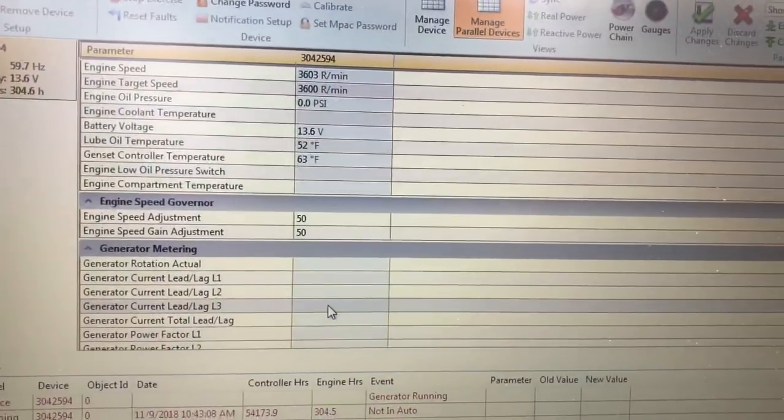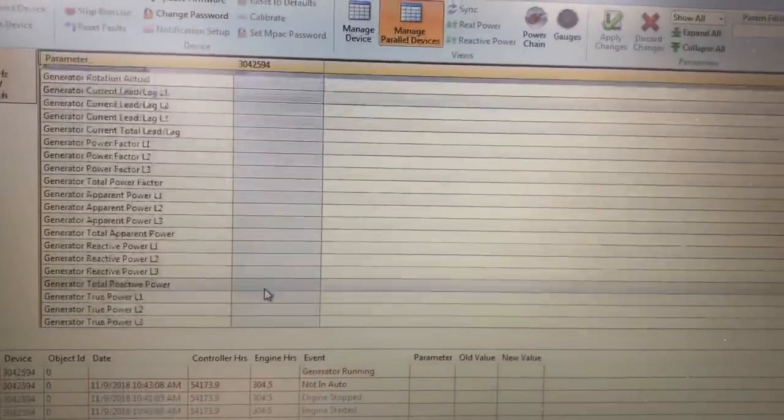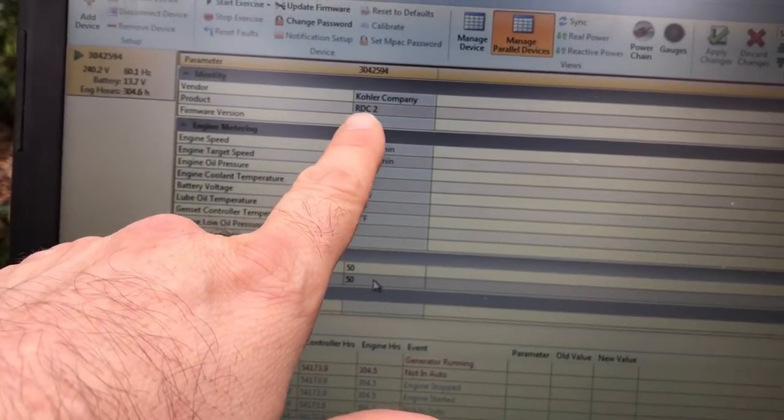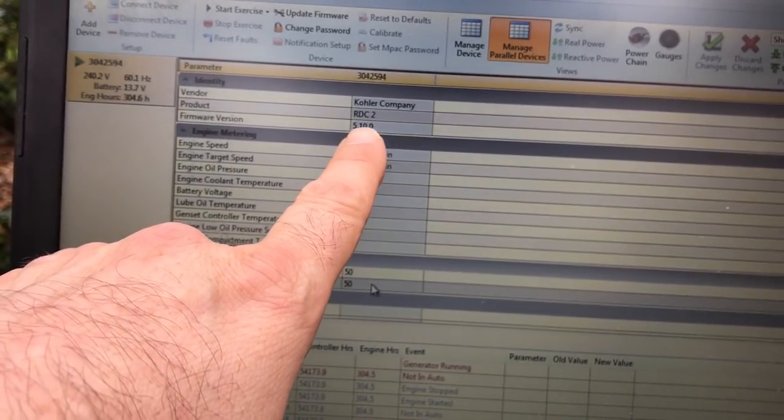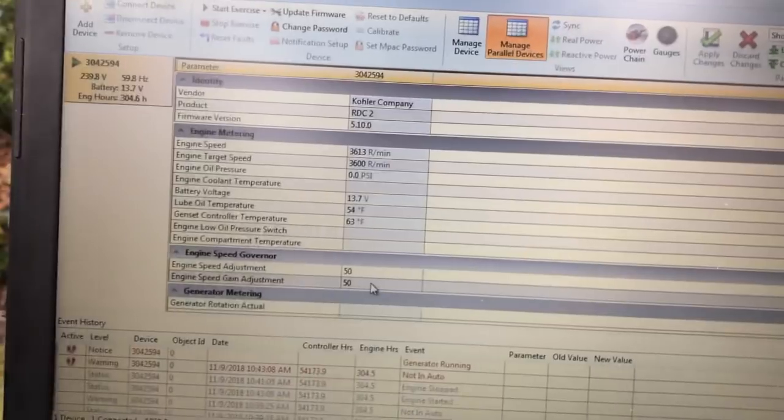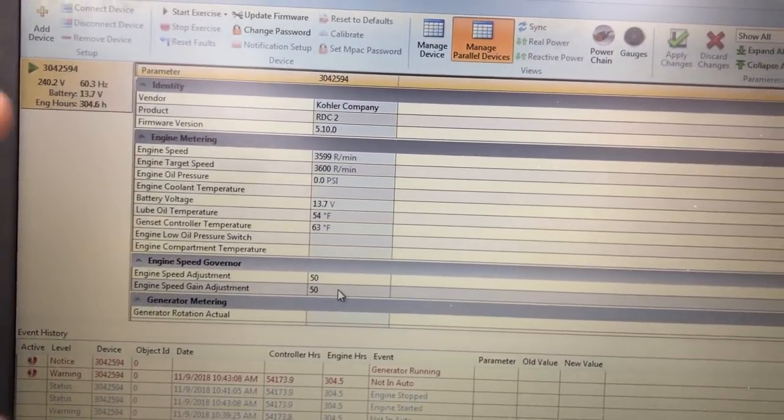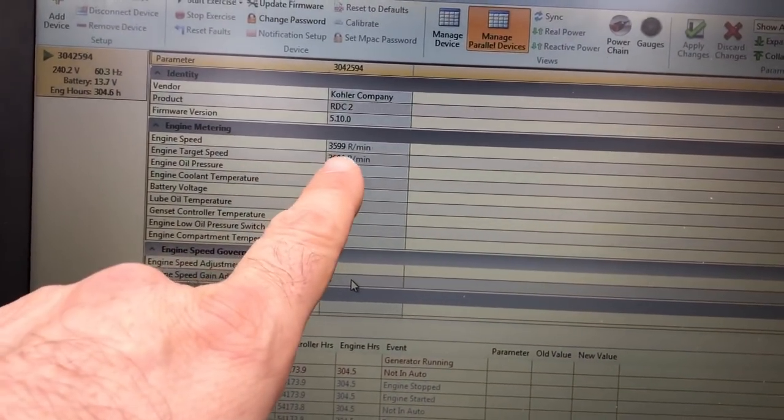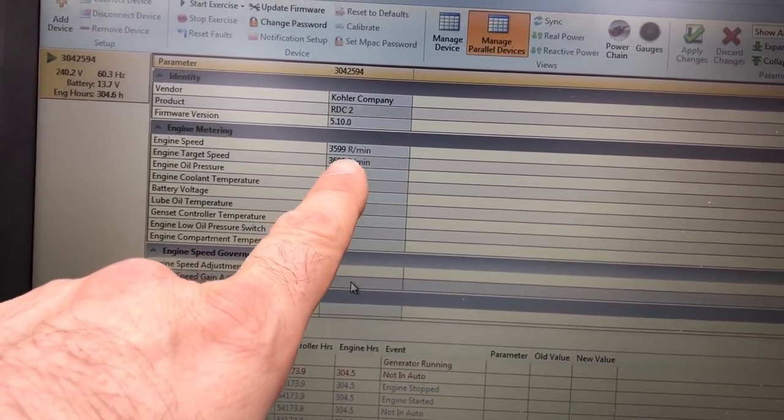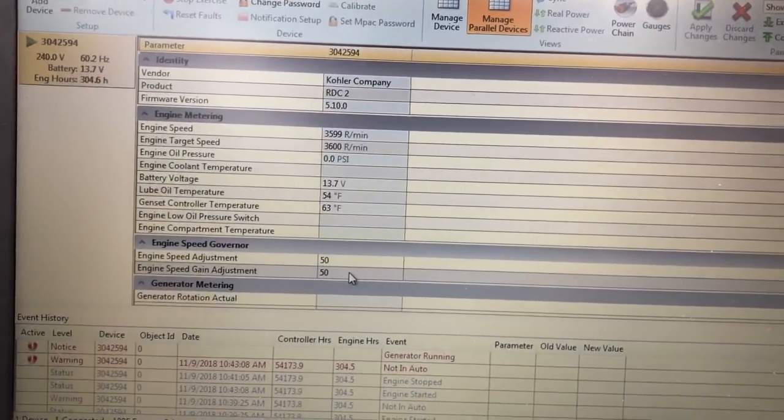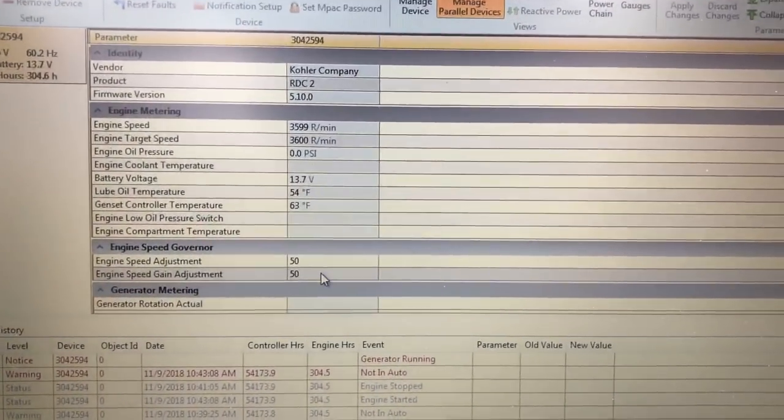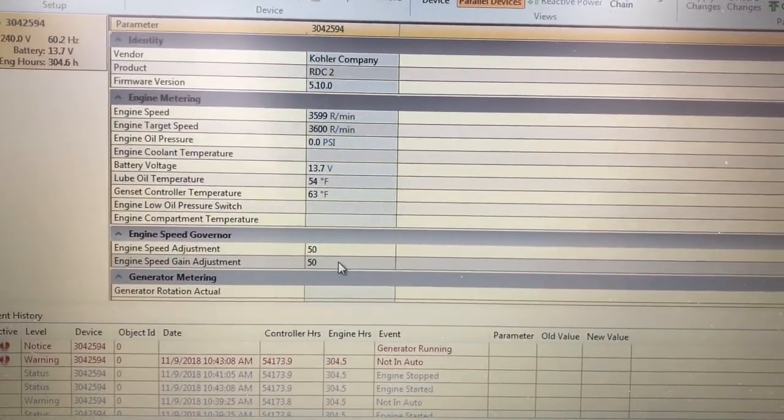Now as you can see, as we start off, it lets you know the brands, the controller that I have there, the firmware, and I'm actually going to be updating the firmware. It's going to let me know my engine speed is at almost 3600 RPM, which is what the generator has to run at to produce a clean 60 hertz.